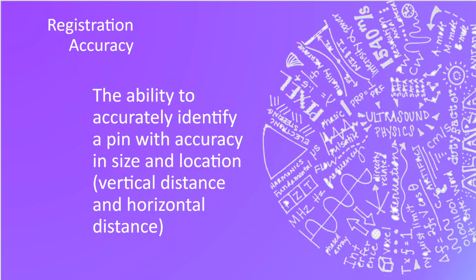The next thing we can test is registration accuracy. So we want to be able to accurately identify pins no matter where they are located within the field, near field or far field. And we want to make sure that we are getting the correct size, no matter if we are in the near field or in the far field. So range accuracy is also known as the vertical depth calibration. Remember, range usually goes in that vertical parallel line.